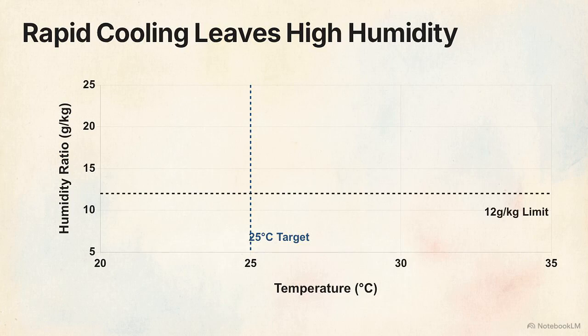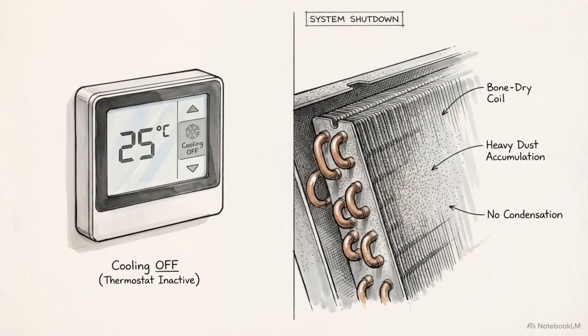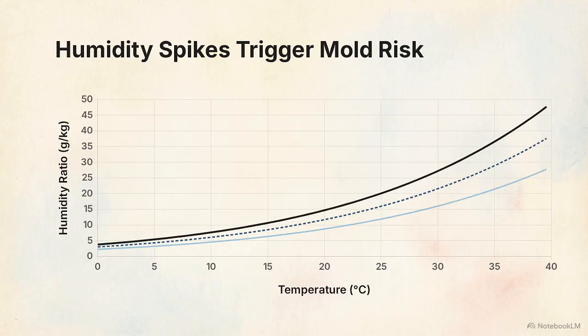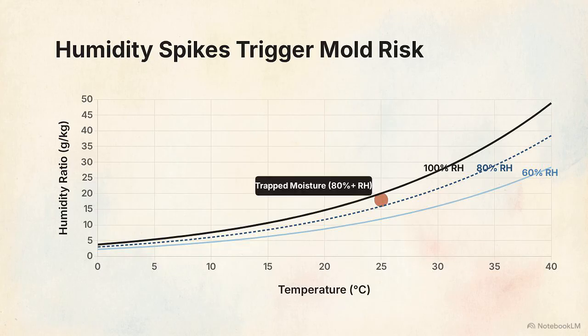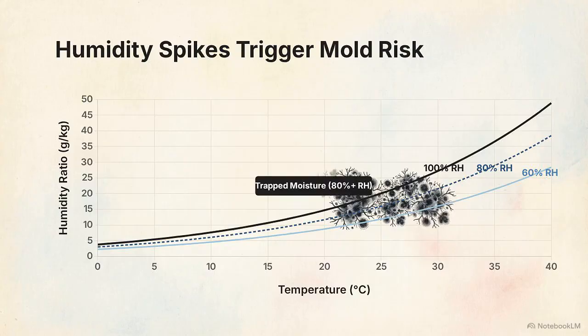When the system turns on, the thermostat is satisfied almost instantly. The cooling process stops abruptly at 25 degrees, but the air still hovers far above our 12 gram per kilogram limit. This causes short cycling. The compressor shuts off long before condensation can even form on the cooling coil to extract the water. The moisture is trapped. Relative humidity spikes past 80%, triggering an immediate risk for mold growth and structural damage.